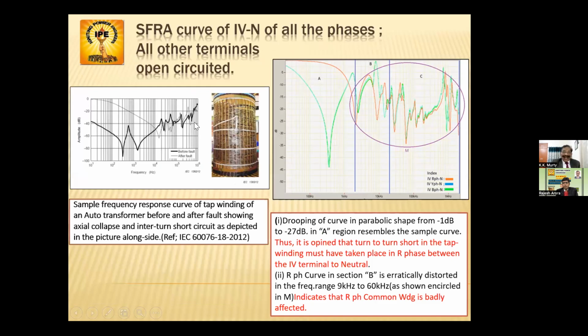Now, this is the next thing. Keeping this IV, the test was taken from IV, keeping all the other terminals floating. Whereas you can see this is as per 60076/18. You can find this. So this is the actual curve. And with the fault, the curve has come like this. The shape has taken. This is the after fault. The curve is after fault.